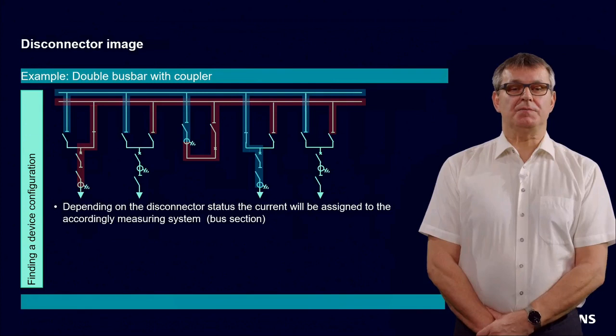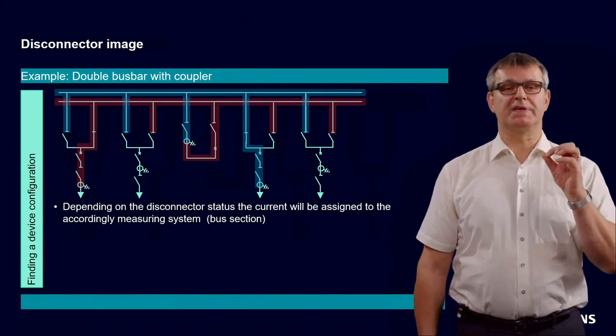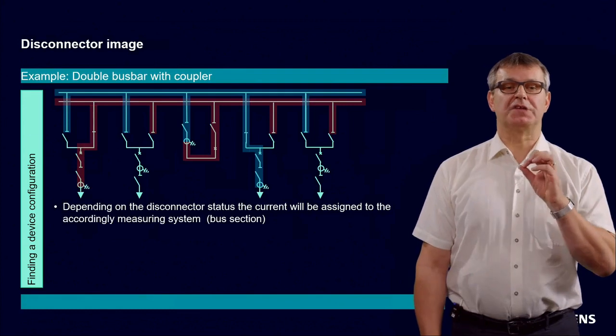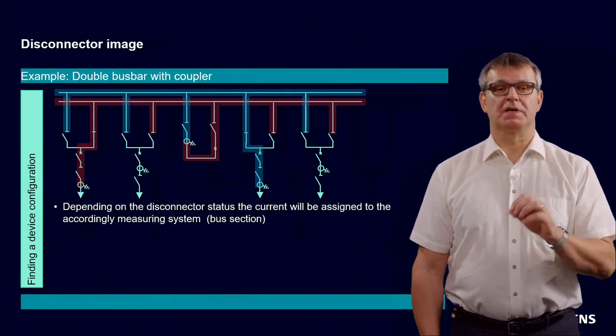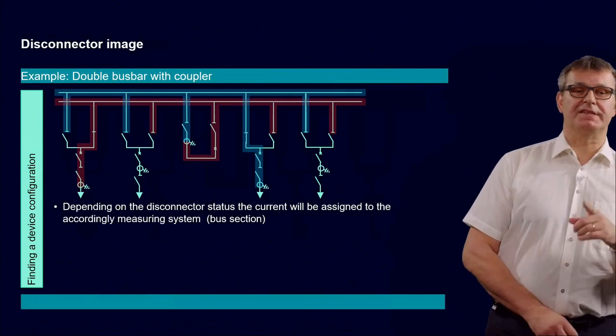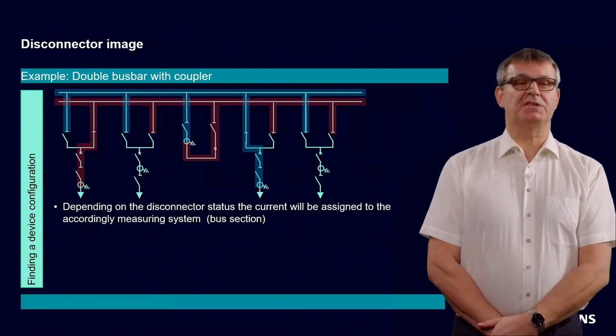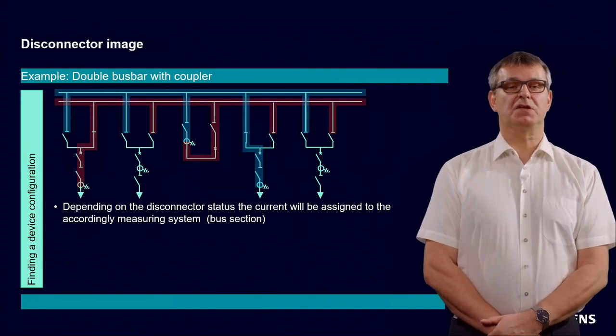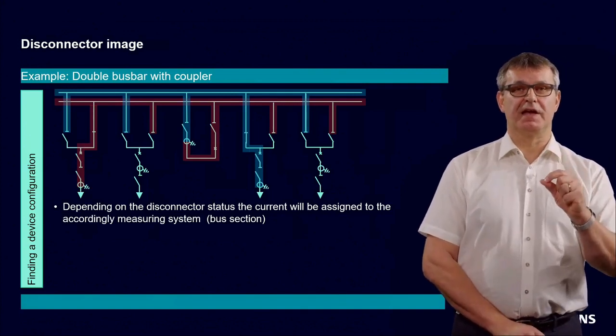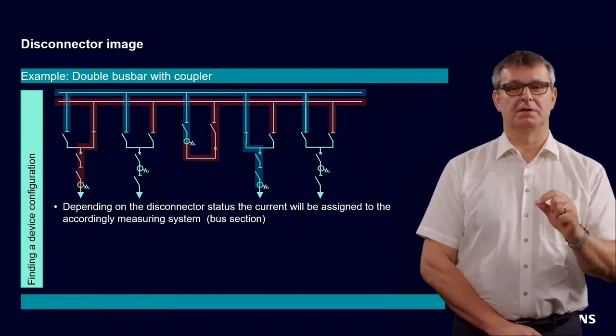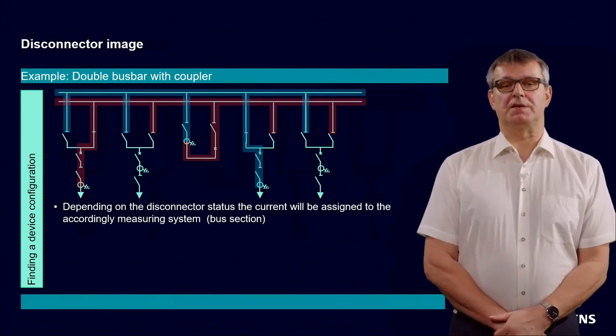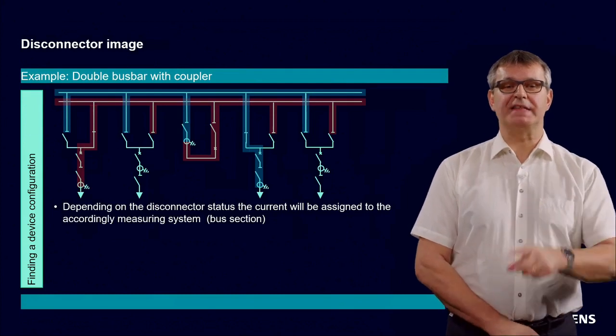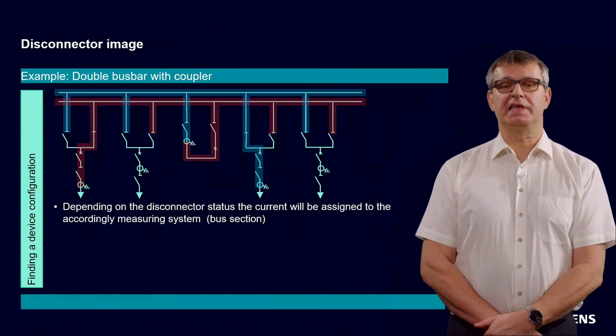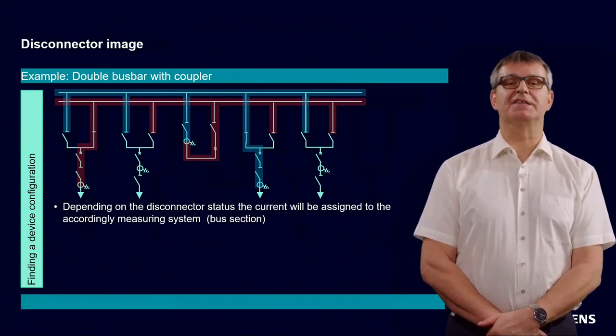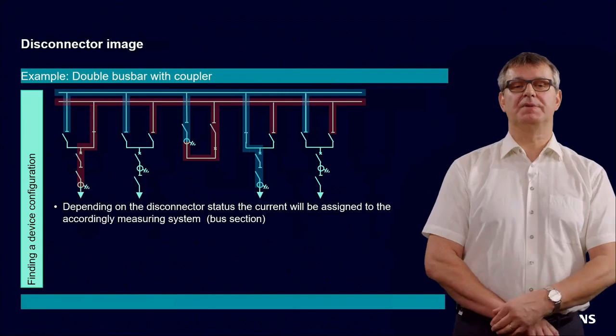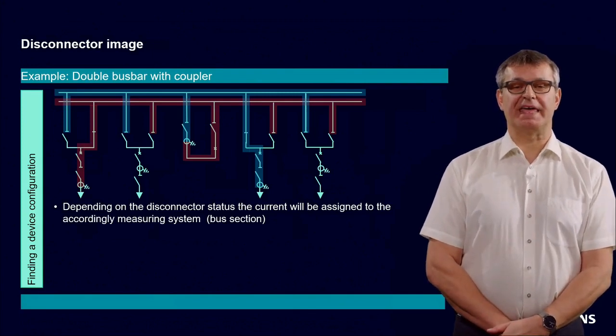Depending on the disconnector status, the current will be assigned to the corresponding measurement system. If you look at the feeder on the left side, the busbar disconnector to busbar B is closed. So this feeder current will be assigned to busbar B. In the other case, the feeder on the right side of the coupler is shown in blue. Here the disconnector to busbar A is closed, so this current will be assigned to busbar A.